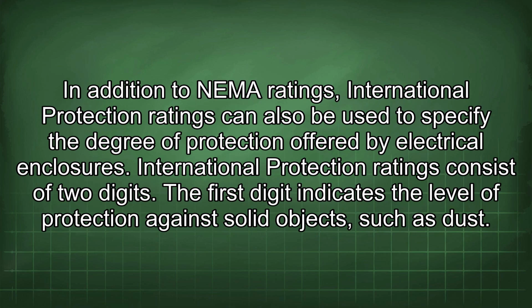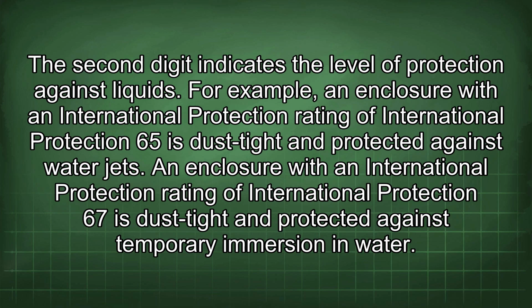In addition to NEMA ratings, international protection ratings can also be used to specify the degree of protection offered by electrical enclosures. International protection ratings consist of 2 digits. The first digit indicates the level of protection against solid objects, such as dust. The second digit indicates the level of protection against liquids. For example, an enclosure with an international protection rating of IP65 is dust-tight and protected against water jets. An enclosure with an international protection rating of IP67 is dust-tight and protected against temporary immersion in water.